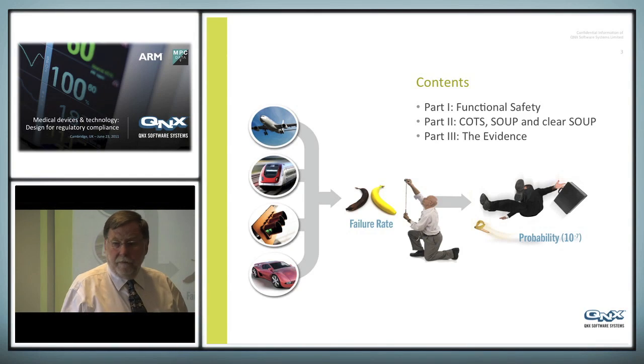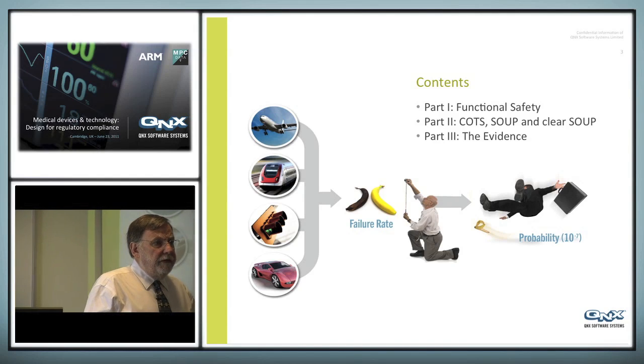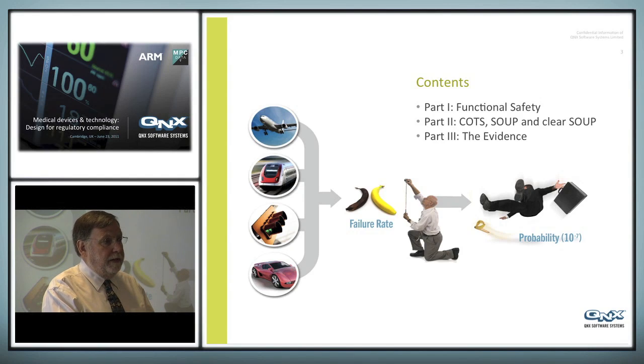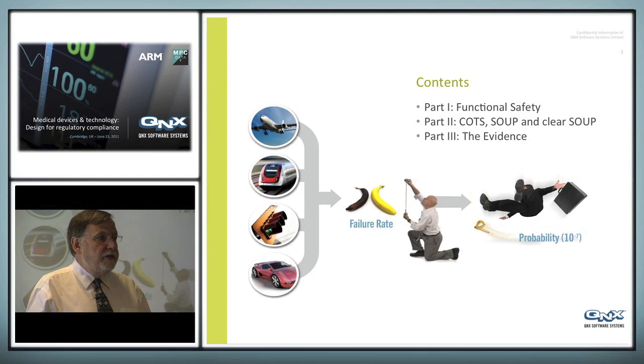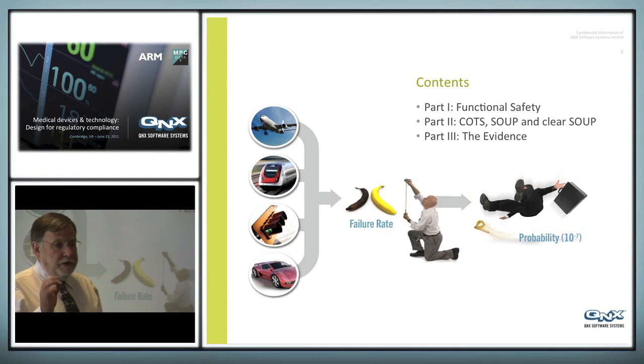The use of COTS, SOUP, and what we've termed 'clear soup' in medical devices, because that complexity means we can't handle everything ourselves — no company can develop everything. And the third area is presenting the evidence. As we move into additional complexity, the evidence we need to present — to ourselves, to your regulatory body, and to your customer — is getting much more complex. It is no longer just process-type evidence; there's going to need to be numerical, statistical evidence about failure rates.